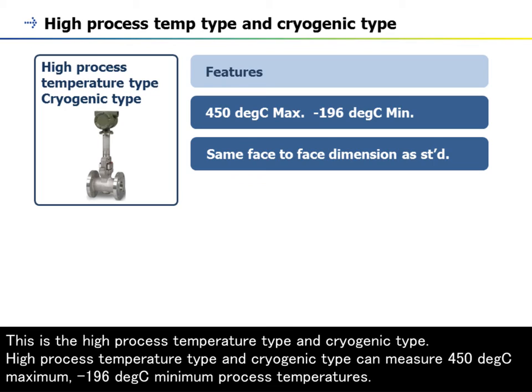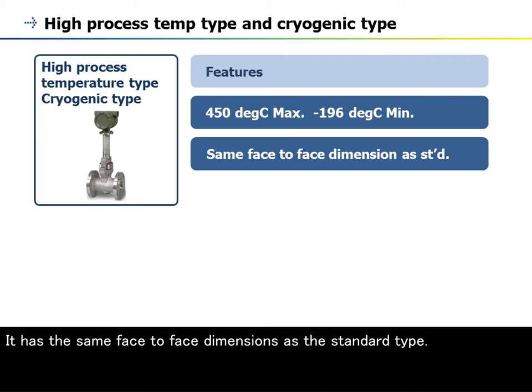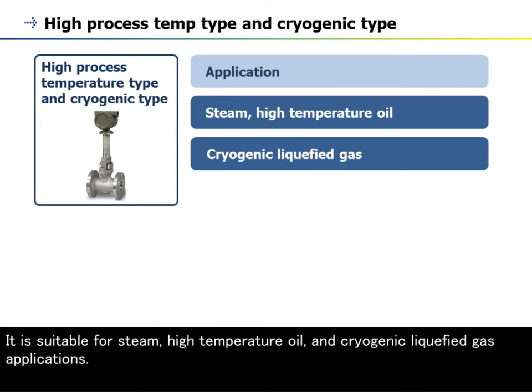This is the High Process Temperature Type and Cryogenic Type. It can measure up to 450 degrees Celsius maximum and minus 196 degrees Celsius minimum process temperatures. It has the same face-to-face dimensions as the standard type and is suitable for steam, high temperature oil, and cryogenic liquefied gas applications.